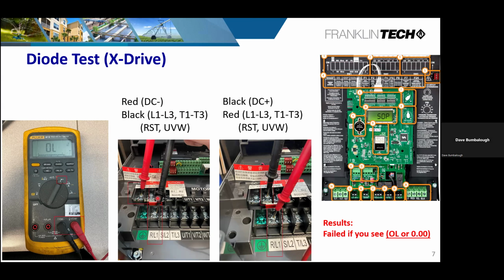Now, the flip side of that is we're going to check the other direction too. So we're going to take the lead from our meter, the black lead, and put it on the positive DC bus. And then we're going to use our red lead and go to the same connection points. We're going to look at L1 through L3, and then also T1 to T3. I'm sorry I don't show you a picture up here of the other side, but it's just right next to where you're checking the input side. The procedure is the same.